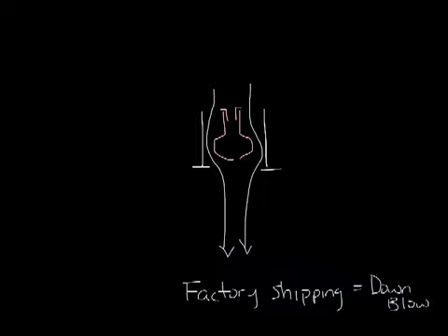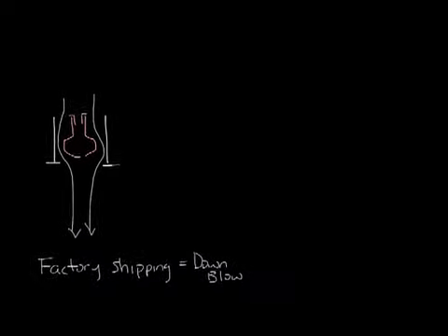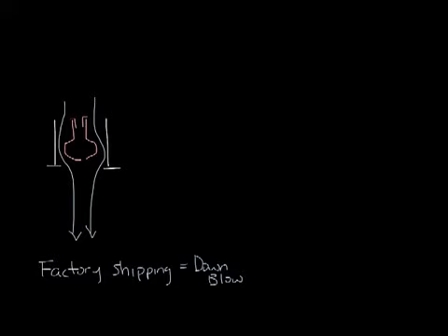So now let's look at how they should be set. So let's move this over a little bit. In my case we weren't on a perimeter so we're looking at a cooling application and it was pointed probably in the factory default straight down at me. So what you really want is for the air to be directed across the ceiling so it can roll the room and mix into the space without dumping on people.